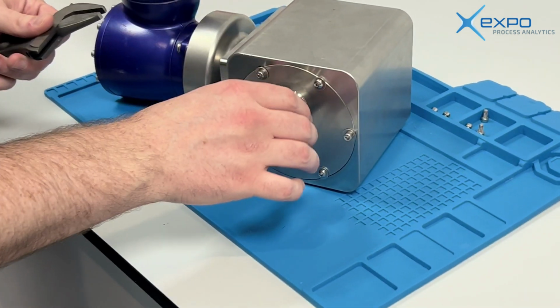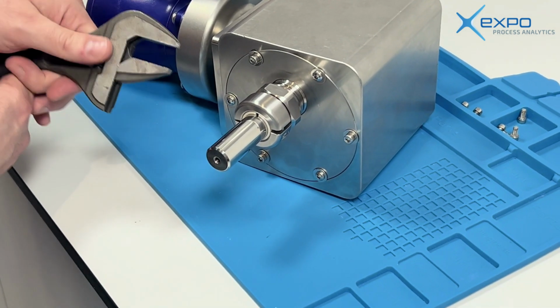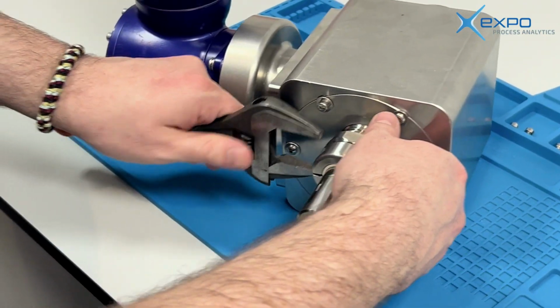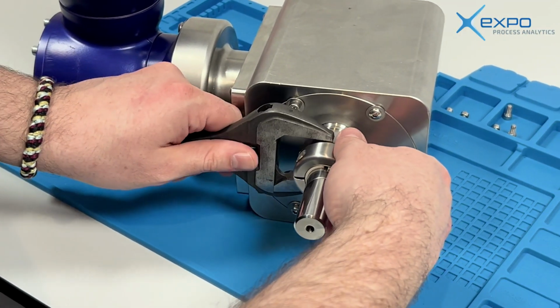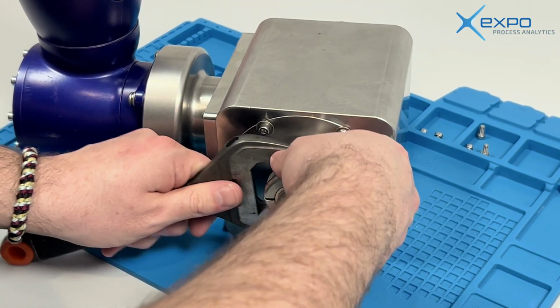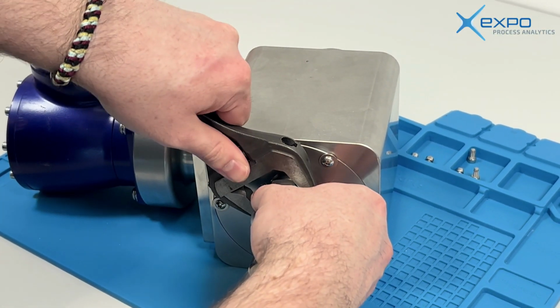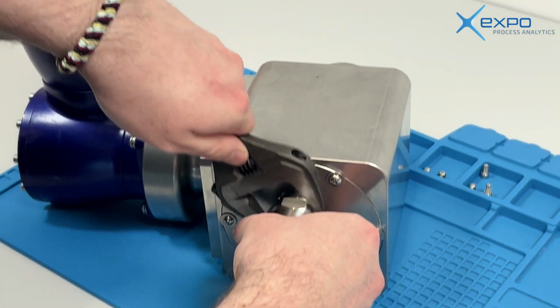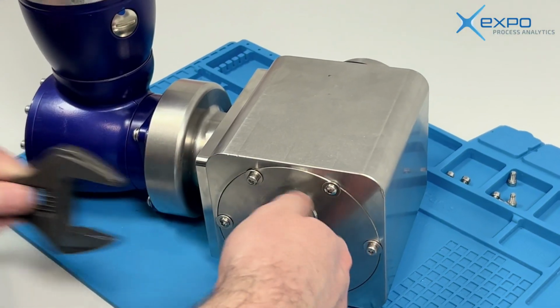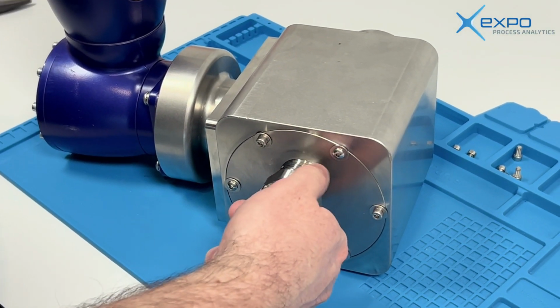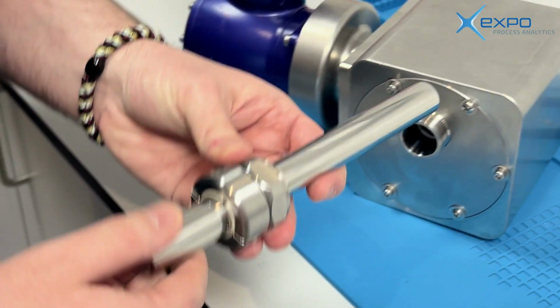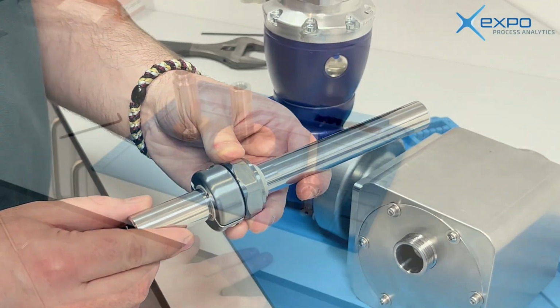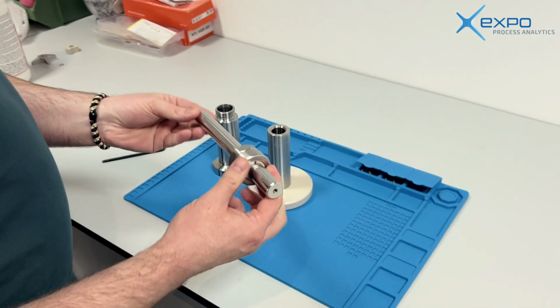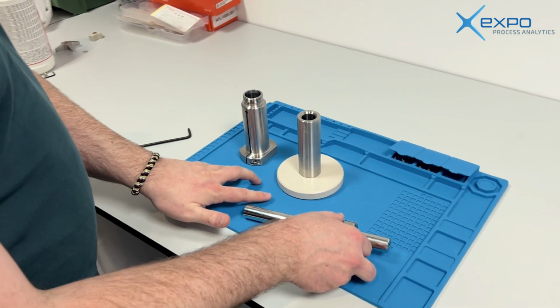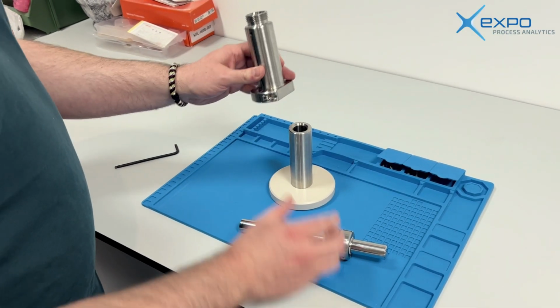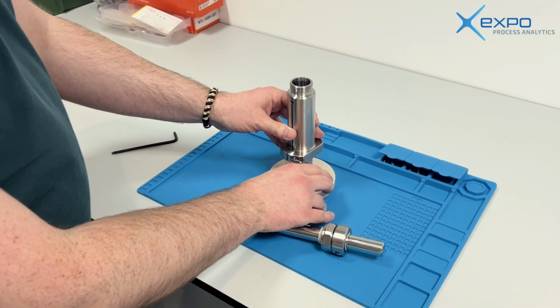Okay, so once the probe has now been clamped at the correct length, you can just undo the compression fitting. Excuse me, undo the retaining nut. And then you can pull this all out like that and transfer it across to the setting tool. Okay, so once you have the depth set on your dummy probe, you can move across to your setting tool components. So what you're going to have is your base and your slider component, which goes over it.